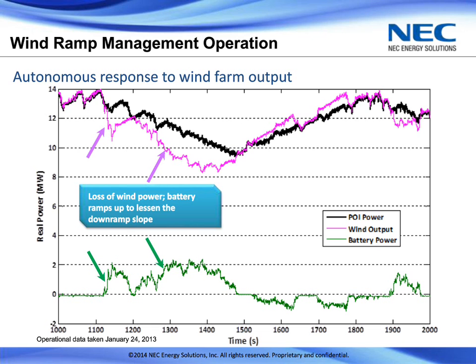The trace at the bottom shows the battery response, holding up the facility output—the point of interconnect power in black. This is not only compensating for changes in the wind facility, but also auxiliary loads within the plant, as far as ramp management. You can see it basically holds a smoother response for the facility, meeting the utility requirements.